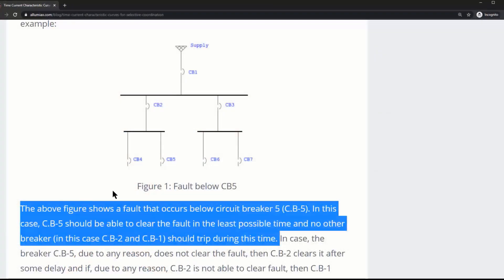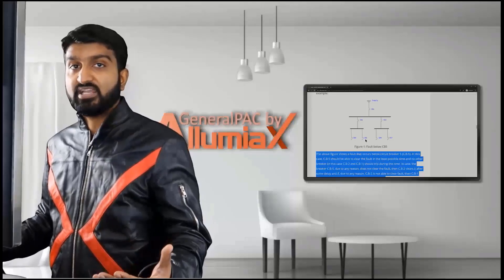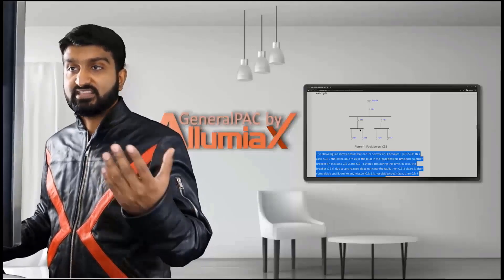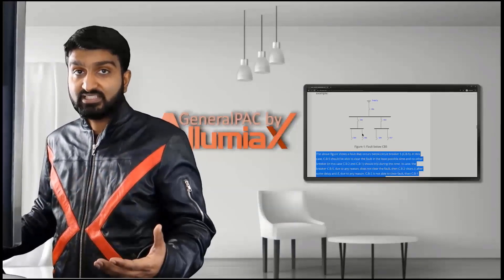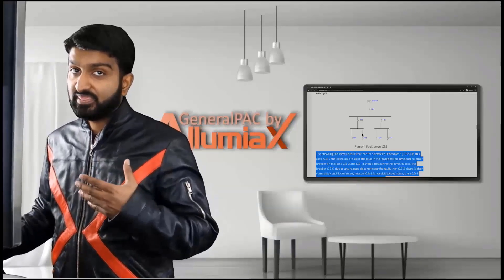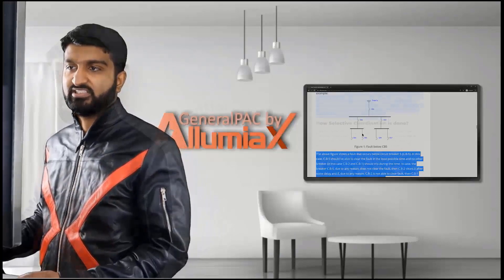So if the fault is beyond CB5, we should expect CB5 to trip and we should not expect CB2 or CB1 to operate. Partial selectivity means that they are coordinated to the best of their abilities but they're not perfectly coordinated.